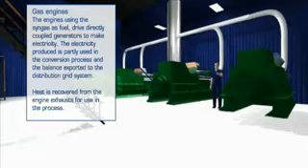The syngas flows into the engines at a constant pressure with the required rate matched to demand. The engines generate power at 11,000 volts. The power is routed to the internal distribution system with the surplus power sold on to the national grid.